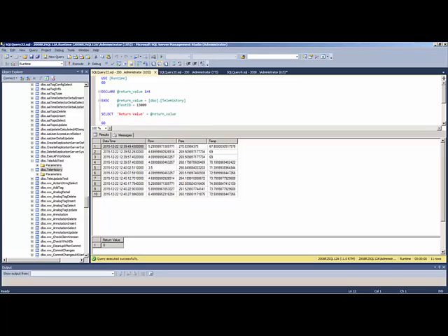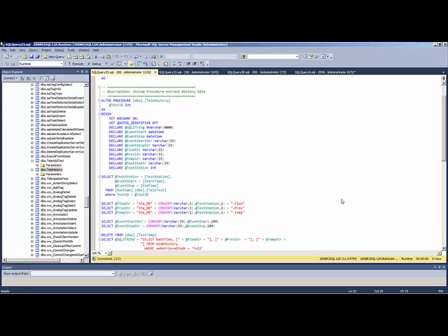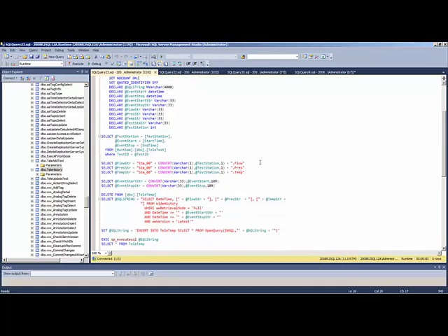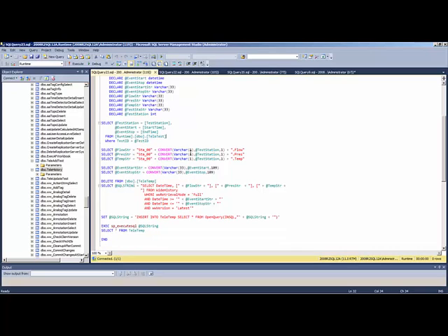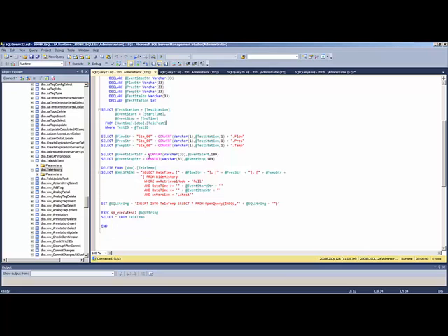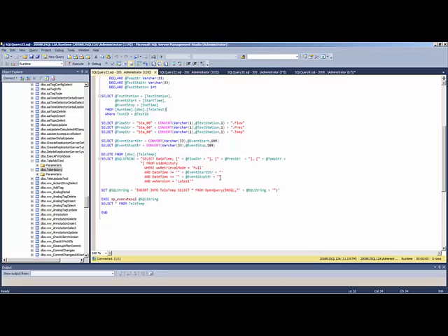Let's take a look at that stored procedure and see how it was done. We're passing in the test ID and declaring some variables used internally. From that test ID we extract the start and end time and the test station number from the test table. We use that information to define the tags we're going to pull, because each test station logs its process data to a different historian tag — whether it's station one, two, or three, it logs data to a different tag set in the Wonderware database. We parse this out, come up with a variable containing those tags, and do a conversion to get the correct datetime format.